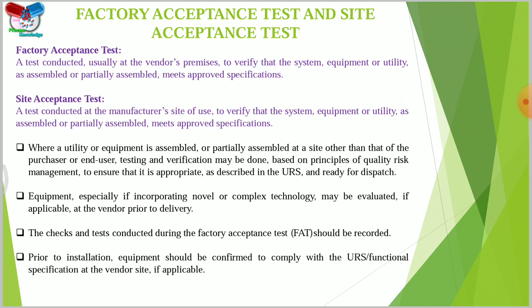The PICS guideline also says about this. The same sentence is given in the PIC/S guide, EU GMP Volume 4, Annex 15 also. The checks and tests conducted during the factory acceptance test should be recorded. Prior to installation, equipment should be confirmed to comply with the URS requirements at the vendor site. This is the requirement of these two.